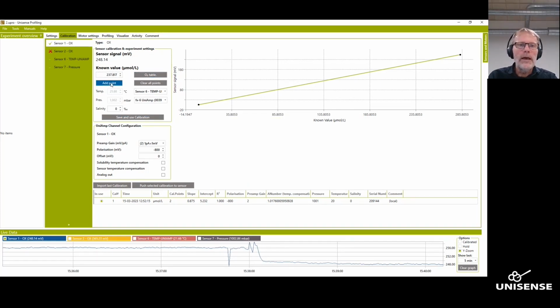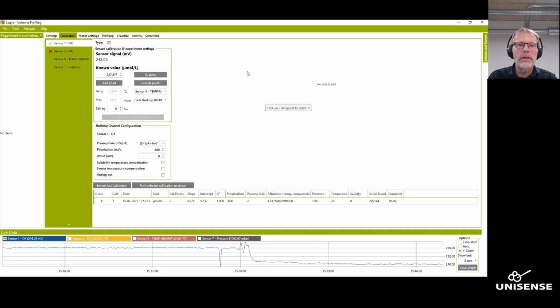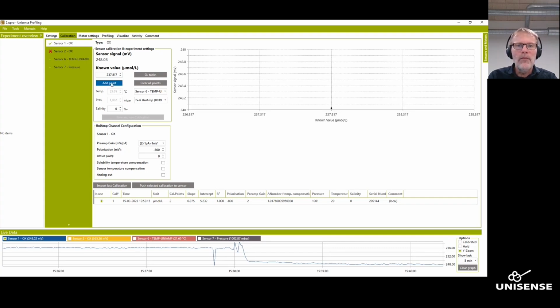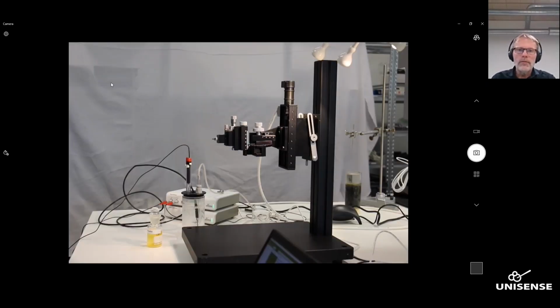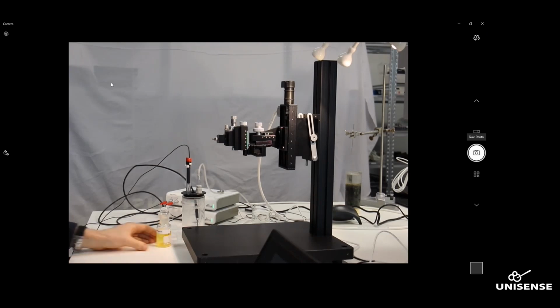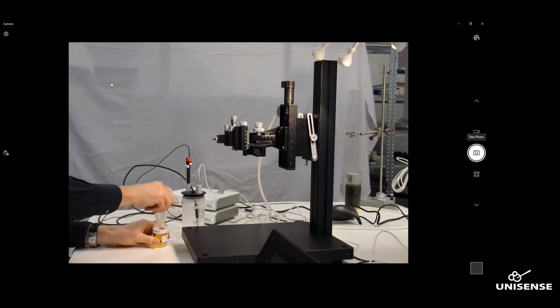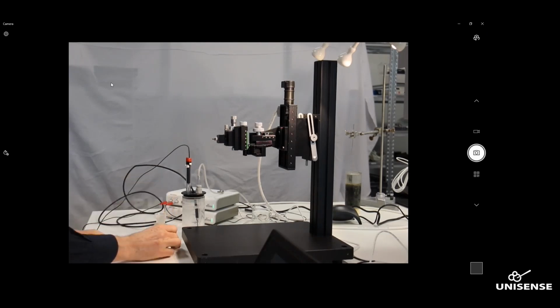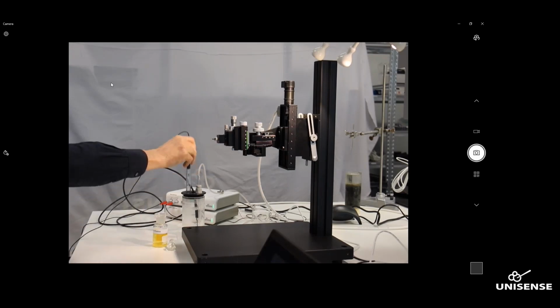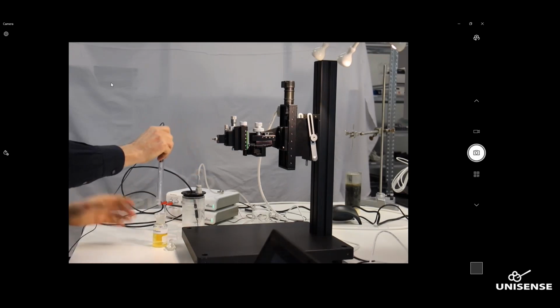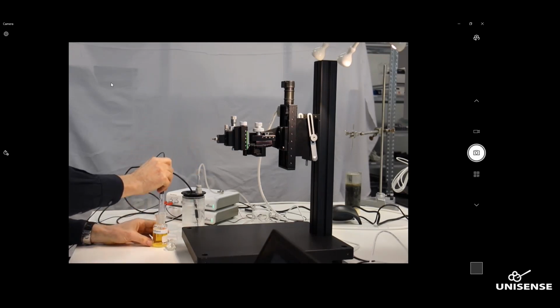Then I just need to add a point. I'll just clear first. I need to clear the old calibration, so I get a blank screen here. Then I can add my point. So now I have one end of the calibration curve. The other end of the calibration curve I will get from an ascorbate solution. I have one here, which is ascorbate has an extremely high oxygen consumption potential. So it's always anoxic, at least for a week or two after you've made it.